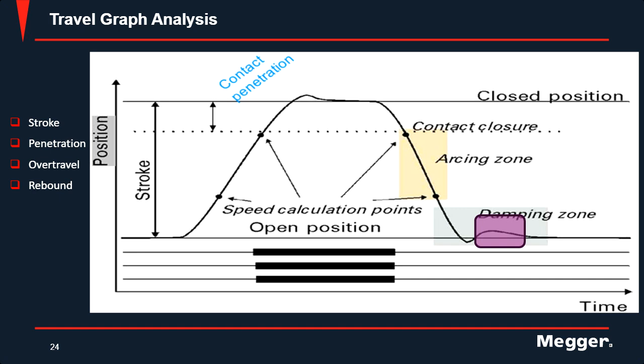And then you have your velocity or your speed. Your velocity can be calculated using speed calculation points. The most common place used for these speed calculation points is your arcing zone, as noted here. It's when it interrupts, it clears the fault. So it's to the point where the main contact leaves and that arcing contact leaves. So at the point of that main contact leaving versus the point of that arcing contact having full separation and the arc extinguishing itself, that's the arcing zone. At the point where the arc starts and the arc ends, you can figure out the velocity of your mechanism.